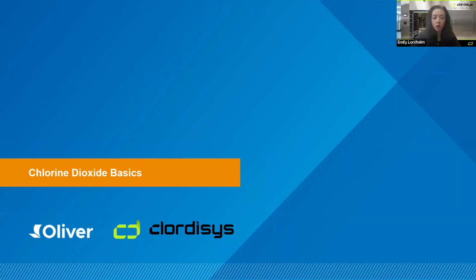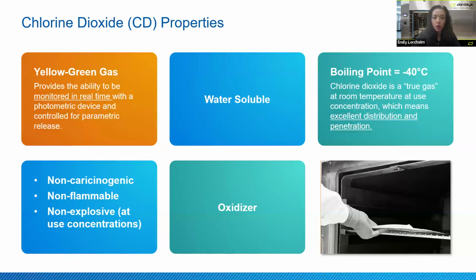Thank you, Haley. So now we're going to talk about chlorine dioxide and the overall background on the technology. So chlorine dioxide has a yellow-green color to it. So if we were to put it in an isolator, so a sealed clear box, you would see that color. And that color is a benefit because we're able to monitor it via UV-vis spectrophotometer. This gives us an accurate concentration and we can calculate a precise dosage off of that. So it's very highly controlled and highly monitored, more so even than ethylene oxide. It's also water soluble, so say there was any water in a chamber, the chlorine dioxide would penetrate and form a chlorine dioxide solution.